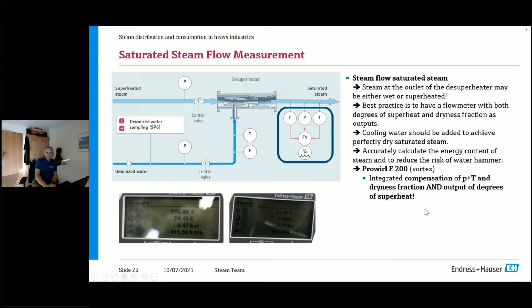We're coming to the saturated steam flow measurement. Here, the best solution again is to compensate by pressure and temperature, because typically that steam is going to be slightly superheated when you get it out, because you have some inlet lengths until you actually reach your point of end use for the steam. So ideally you would allow for some degrees C of superheat here. But in some cases, if you add too much water, what's going to occur? You're going to see wet steam. And our Prowirl F200 is really ideal for such an application, because on its display and on its output, you can assign the dryness fraction and the degrees of superheat. So it's a quality meter that happens to measure flow as well, so to speak.